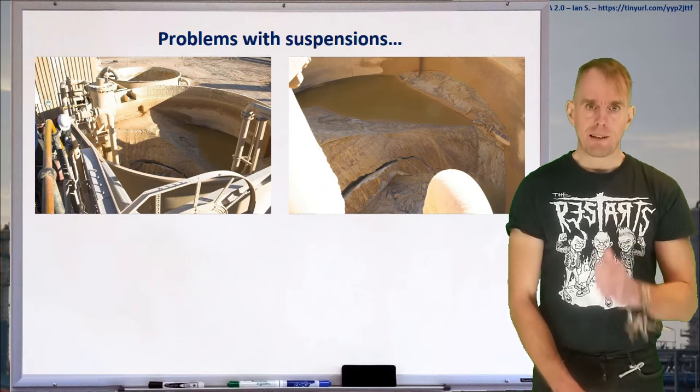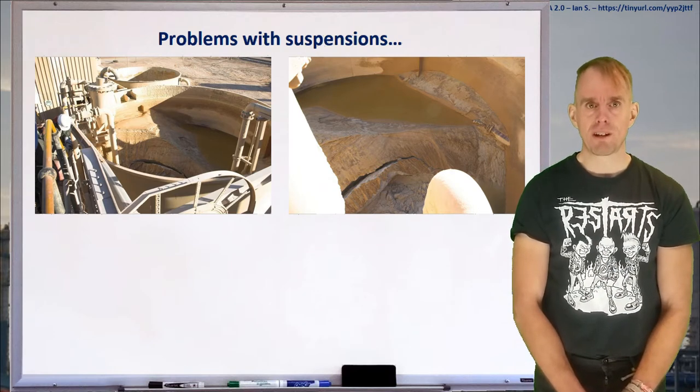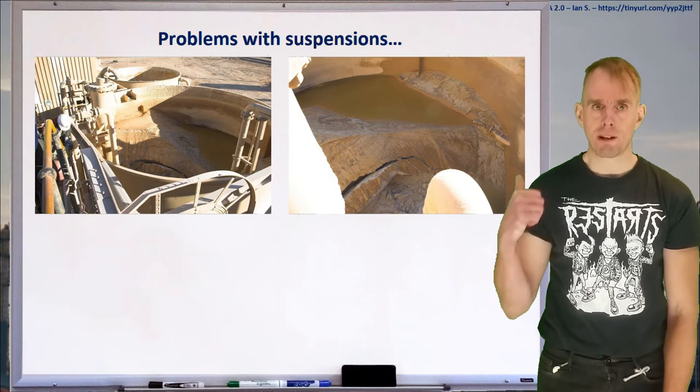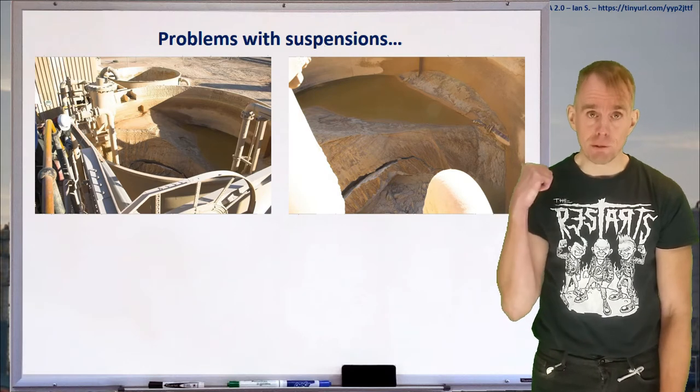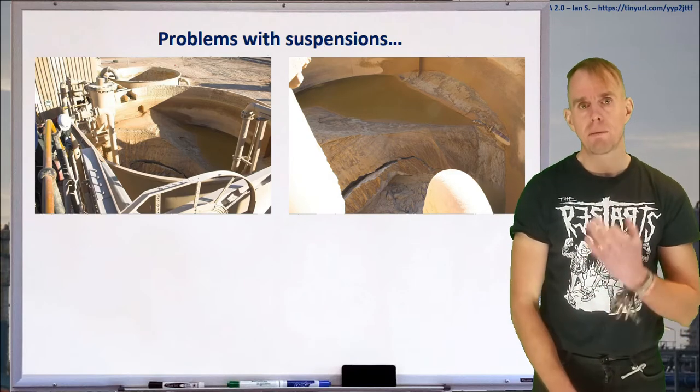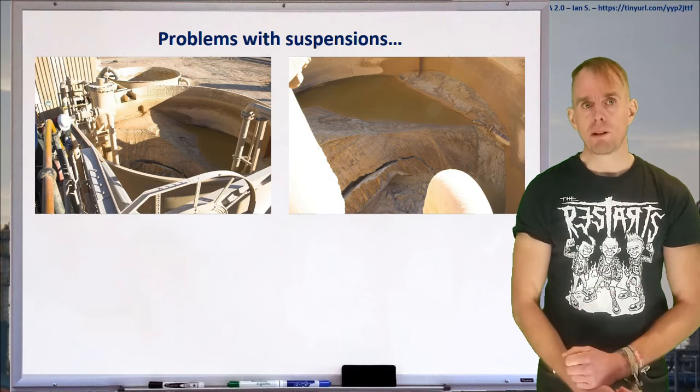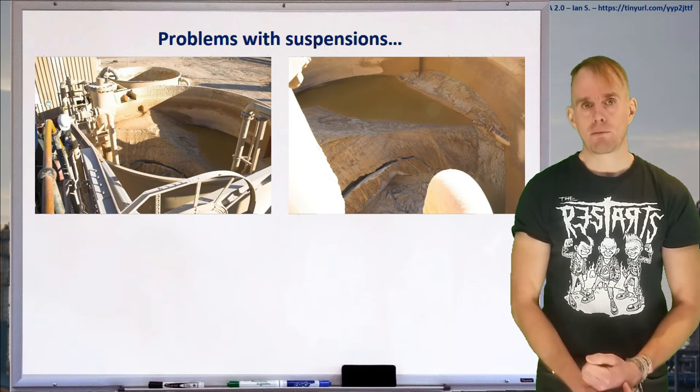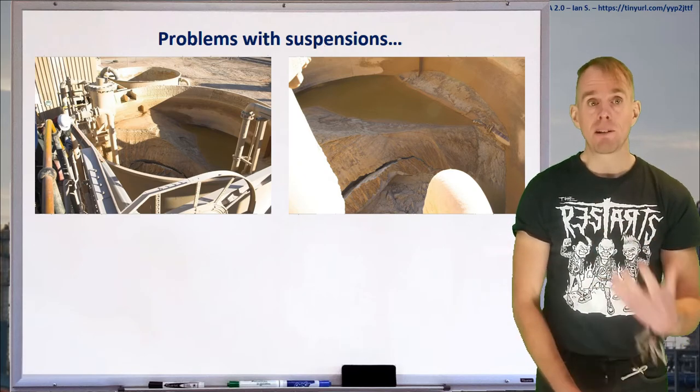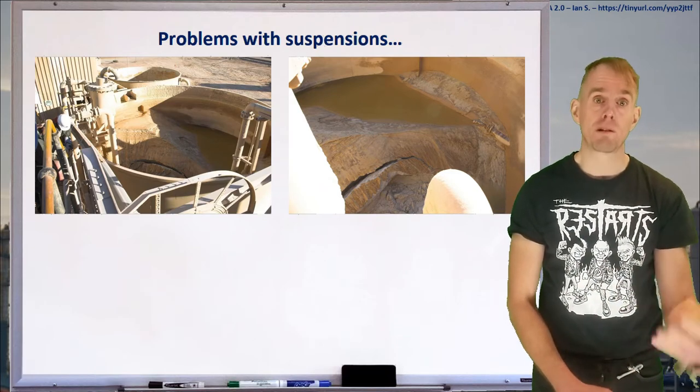So, key point here. Learn from other people's mistakes. If you're dealing with suspensions of solids, do not allow your solids to settle out. And if you're dealing with suspensions of solids, ensure you've designed into your system plenty of means of de-blocking it. Design in wash points. Design in easy access points. Design in bypasses, if needs be, to bypass pieces of equipment that are blocked, such that you can keep your process going.